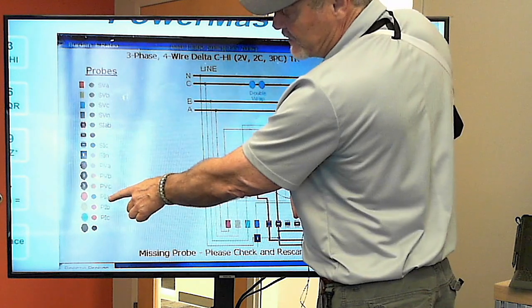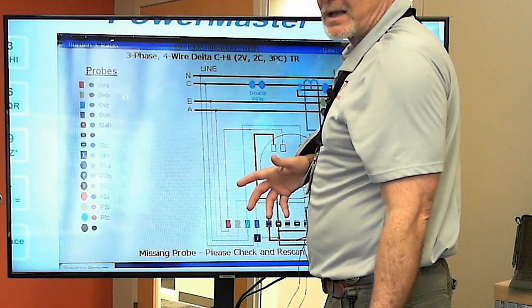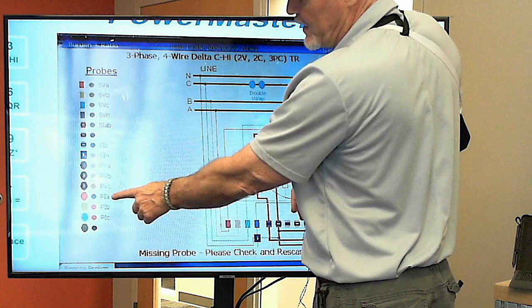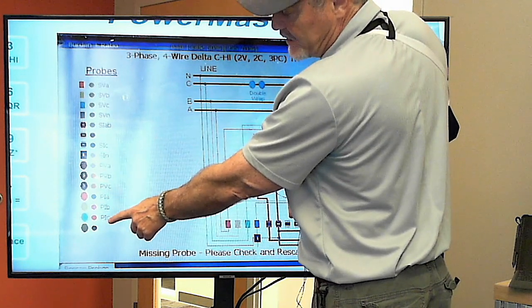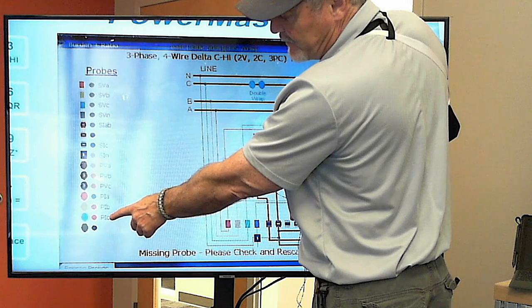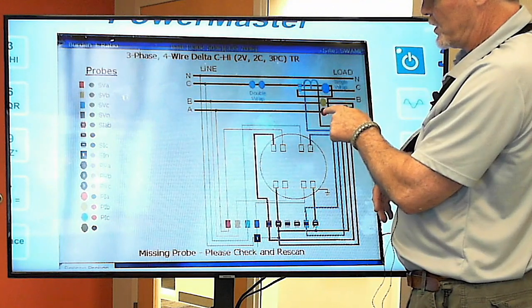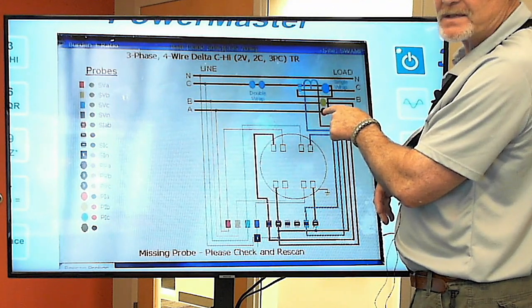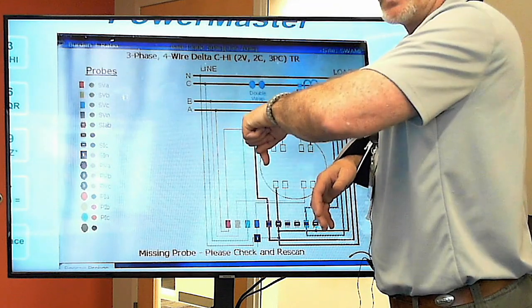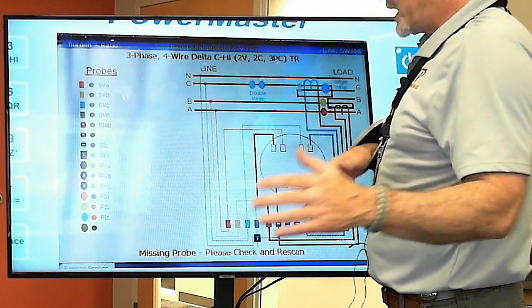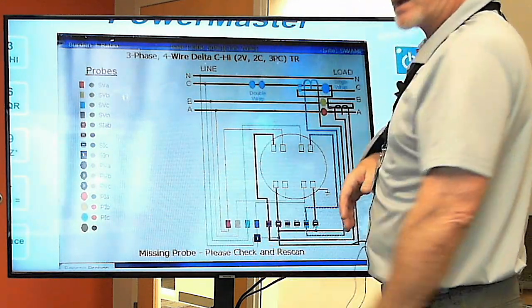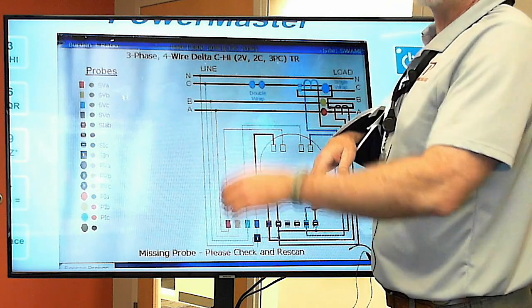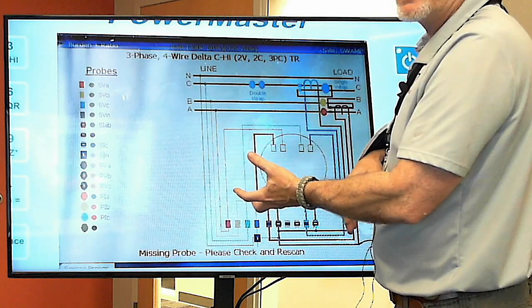You leave it connected just to the cable on A phase, and you move the probe up to B and then to C. So you'd leave it connected here on primary current A. That's fine, except it's giving you red for primary B and primary C because it's looking for my other two flexes, and they're not connected to the cable, so the machine's saying you're missing some probes, so it won't let you continue. That's why we've got to change that.